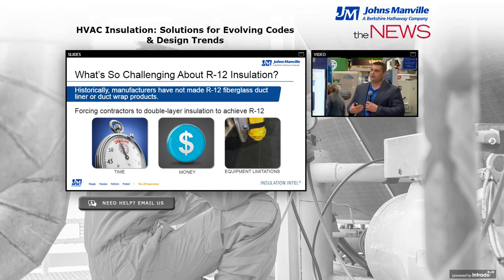Basically, if a contractor was requested to do an R12 type solution, they had to double layer insulation—take a layer of unfaced fiberglass without the vapor barrier, wrap that duct or use spin glass board, then come back and reapply with an FSK-faced product, combining an R4 with an R8, or two R6s, however they needed to reach the R12 required at installation. That's a lot of time on the labor side—double wrapping, double insulation—and it costs a lot more because you're asking for a lot more insulation to wrap the job. There were also some things, especially on the liner side, that we had to develop around equipment limitations when it came to pinning ductwork and pinning liner.